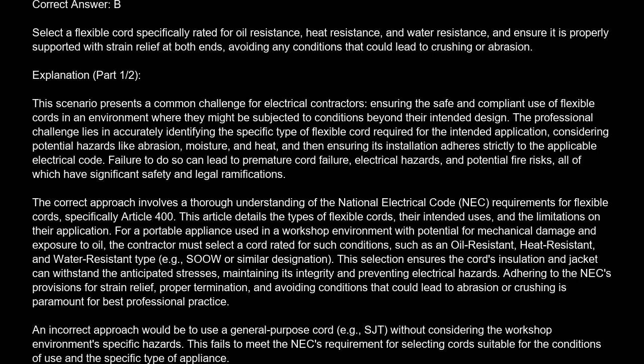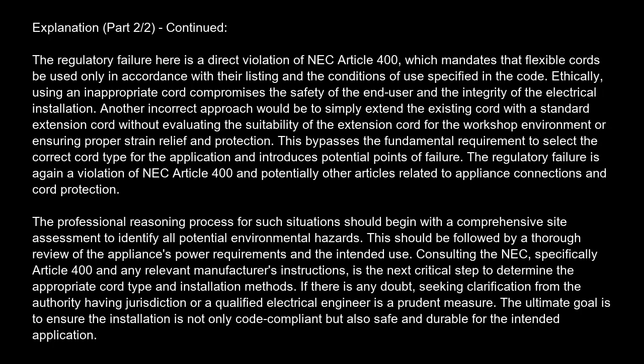An incorrect approach would be to use a general-purpose cord, e.g., SJT, without considering the workshop environment-specific hazards. This fails to meet the NEC's requirement for selecting cords suitable for the conditions of use and the specific type of appliance. Regulatory failure here is a direct violation of NEC Article 400, which mandates that flexible cords be used only in accordance with their listing and the conditions of use specified in the code. Ethically, using an inappropriate cord compromises the safety of the end user and the integrity of the electrical installation.